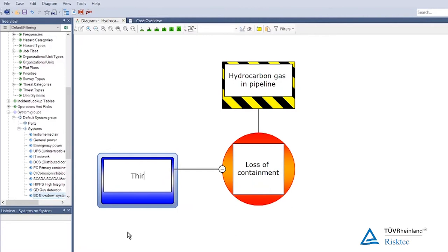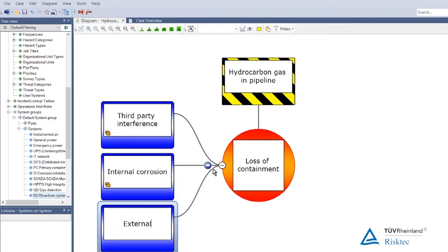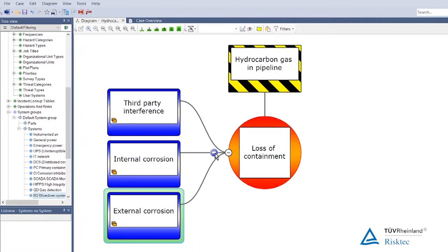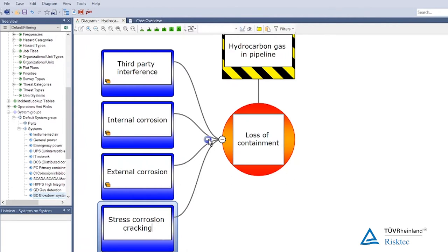Third party interference could be a cause. Internal corrosion might give us a potential for release. External corrosion also. We would actually split it to identify internal corrosion and external corrosion and then standalone stress corrosion cracking, as stress corrosion is very much in vogue at the moment.